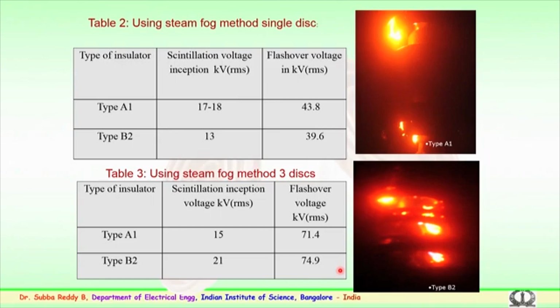So, it is to be noted here, in case of a single disc for type A1 the flashover voltage was somewhere near 44 kilovolts, but in case of 3 discs it should have been 120. So, it is not that the phenomena, the surface discharge, the scintillations which are happening further depending upon the stress, the entire creepage bridges at 72 kV.